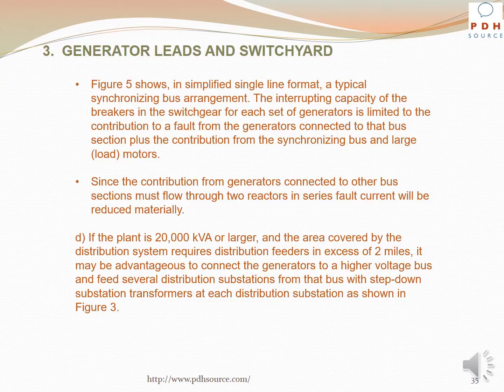Figure 5 shows, in simplified single-line format, a typical synchronizing bus arrangement. The interrupting capacity of the breakers in the switchgear for each set of generators is limited to the contribution to a fault from the generators connected to that bus section, plus the contribution from the synchronizing bus and large load motors. Since the contribution from generators connected to other bus sections must flow through two reactors in series, fault current will be reduced materially.